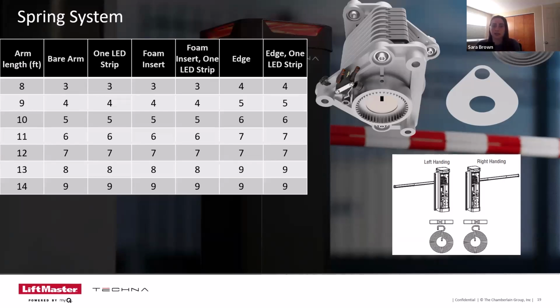If you do need to change the handing, there are arrows on the springs, and the arm direction should match the direction of those arrows. It comes standard right-handed, which covers about 80% of applications. But if you have a left-handed application—meaning if you're standing at the cabinet with the lid open and the arm will face left when it's down—you take out the 3 bolts in the back, flip or rotate it 180 degrees, and replace those bolts in the same 3 spots. That's all you need to do to change handing.